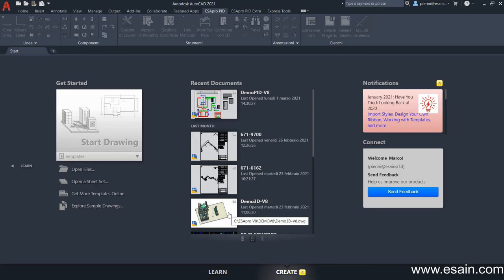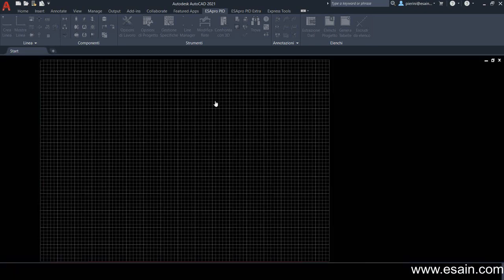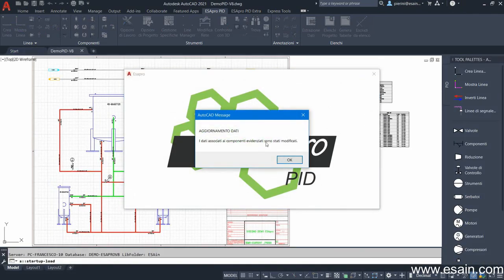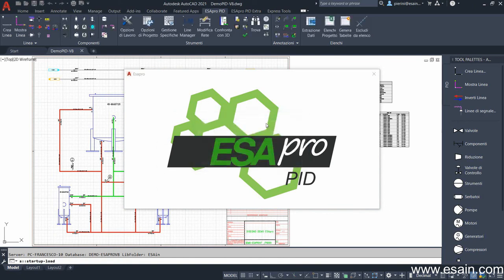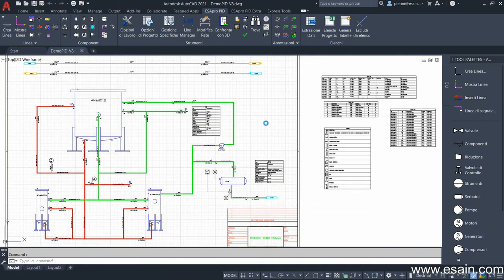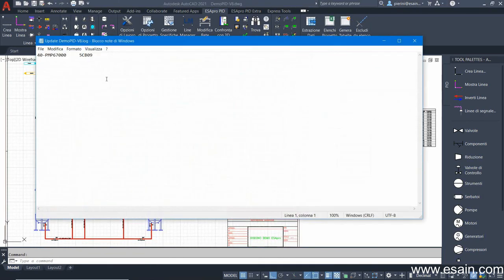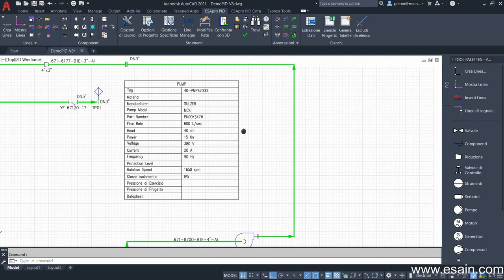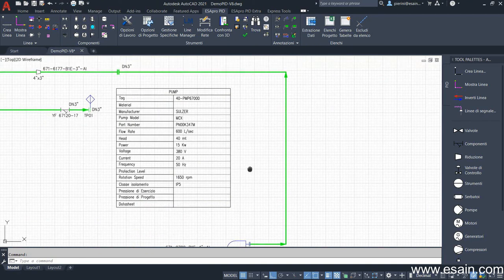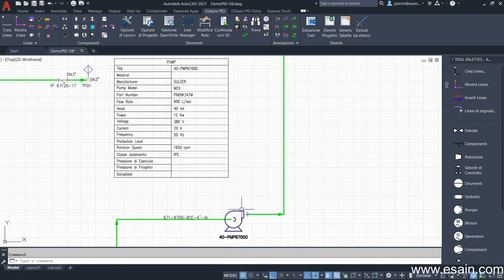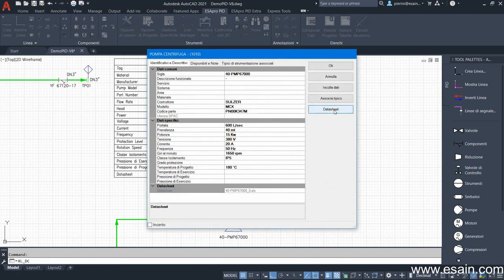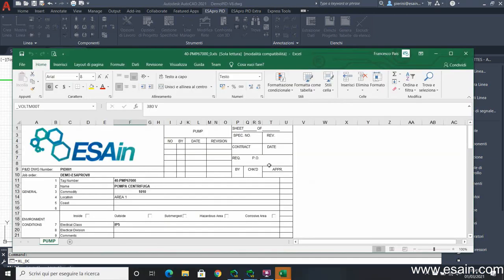Once finished my work in ESApro instrumentation, let's go back to ESApro P&ID and see what happened. Open the scheme. A notification appears showing me that the pump has been modified by instrumentation. This is the item being modified. If I check the data table, we see that the pump data has been updated correctly. Double-clicking, we can see that the datasheet has been linked to the P&ID item, and clicking on the datasheet button, I can open in read-only mode the Excel document.